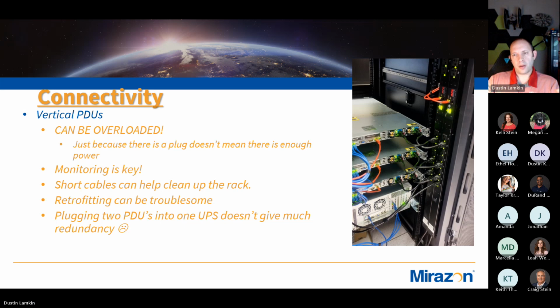The other recommendation I give out a lot is make sure you get short cables. It might seem silly since we all have these cables sitting around, but short cables tremendously help with airflow in these racks. That helps keep your heat down and keeps your power consumption down since fans aren't spinning up as much to cool things down. It keeps everything nice and clean, and you don't accidentally pull the wrong cable that's wrapped around another and yank power from the wrong server—that happens all the time. So short cables are super awesome.